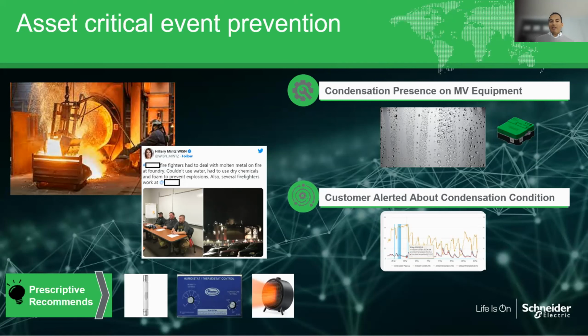And they had enough condensation present that it was going to create another explosion. By the time we started helping this customer, they told us, hey, we have a problem, we can't put a finger on what this is. We instrumented this transformer, started pumping data to the cloud around the sensors, the meter monitoring this medium voltage switch.